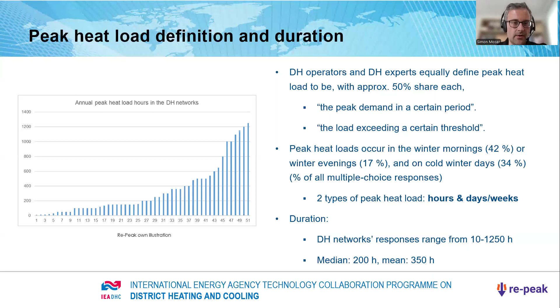We also asked when the peak heat load time occurs. We see two different types: peak load that occurs for some hours, especially winter mornings or evenings, or longer-term harsh weather lasting days or weeks, where it is really cold compared to the rest of the year. We asked how long the duration is in your network, and responses range from as little as 10 hours up to 1,250 hours per year. We see a median value of 200 hours and a mean value of 350 hours per year defined as peak heat load by district heating operators.